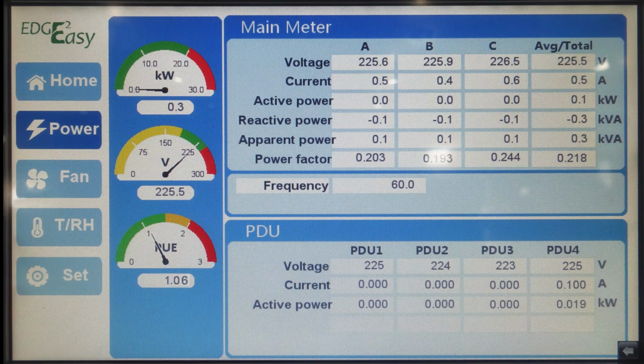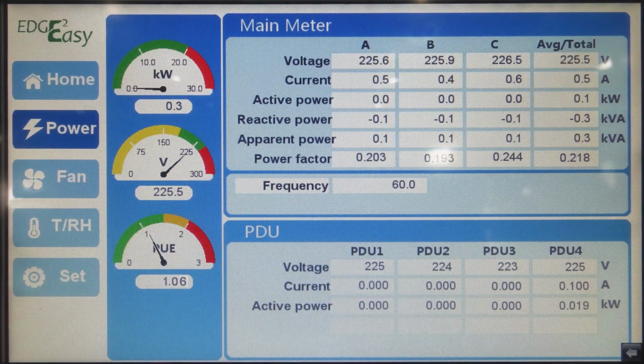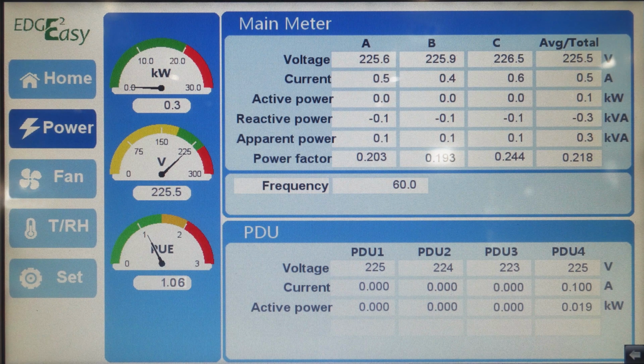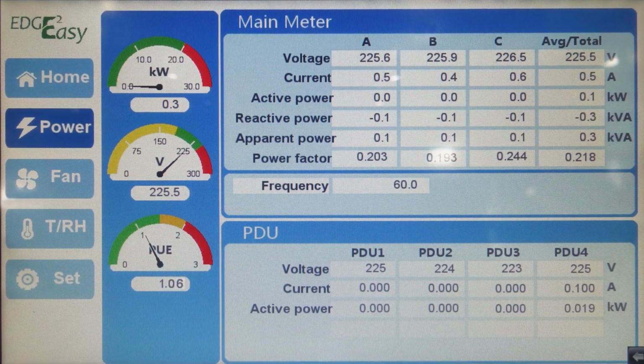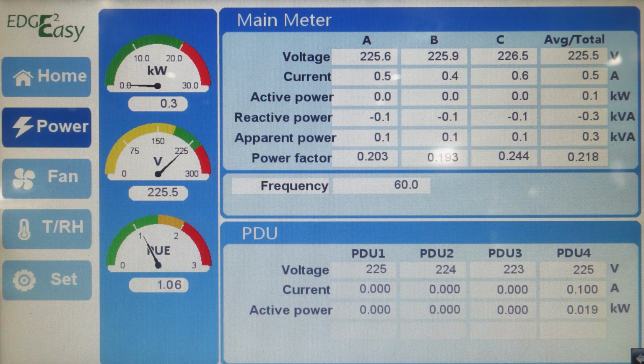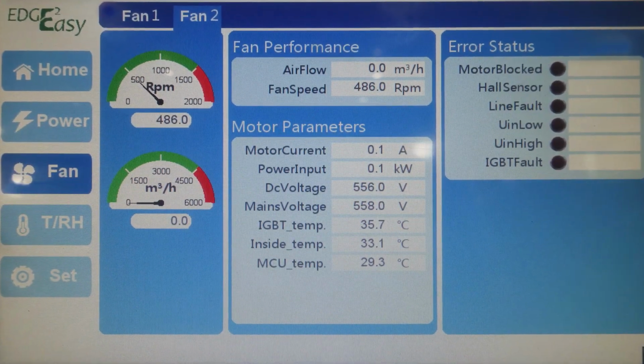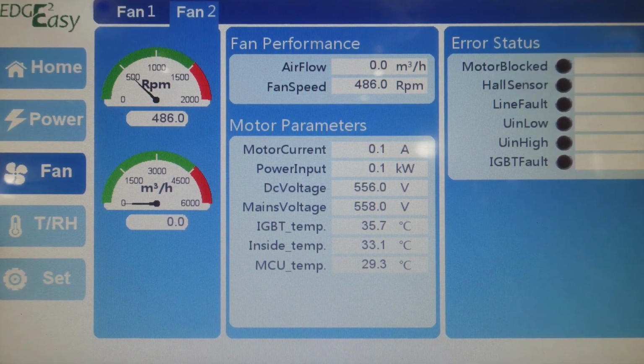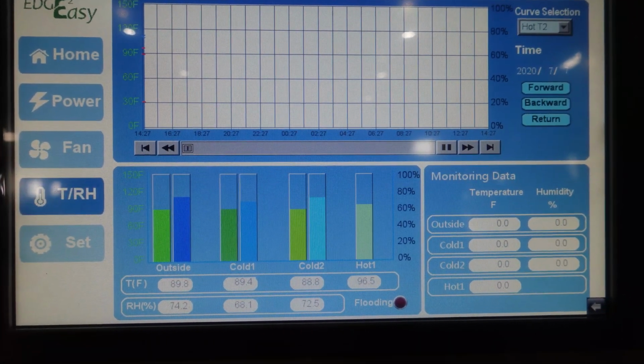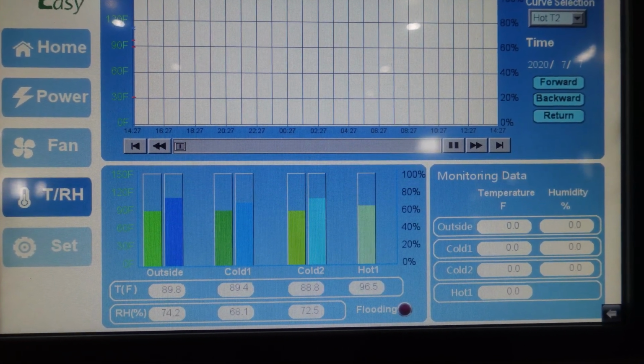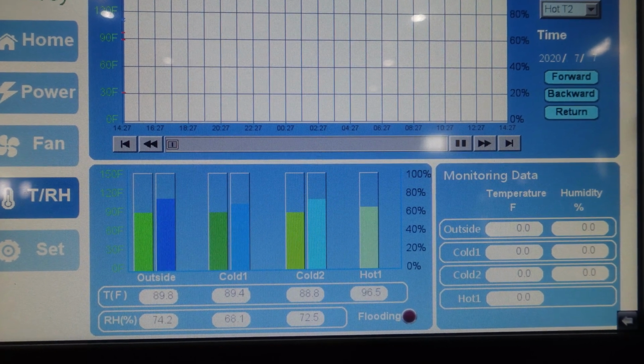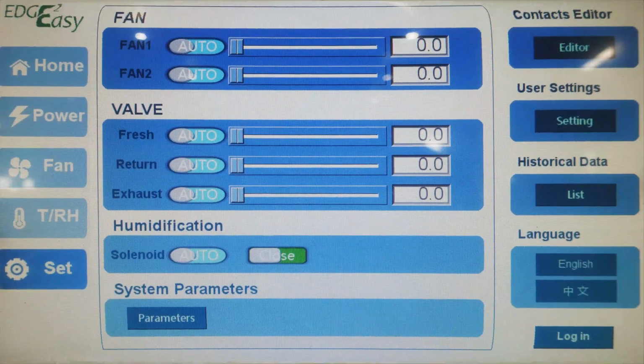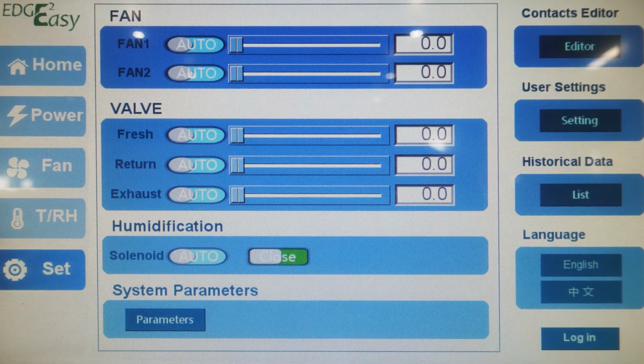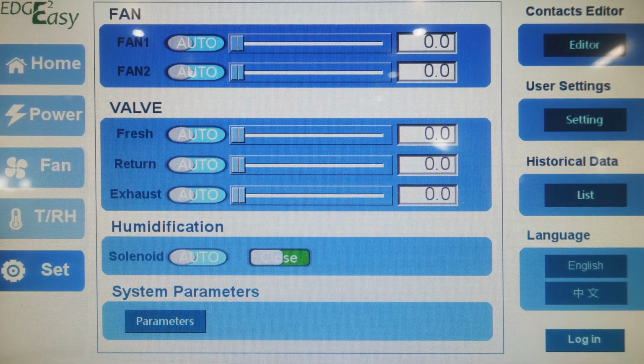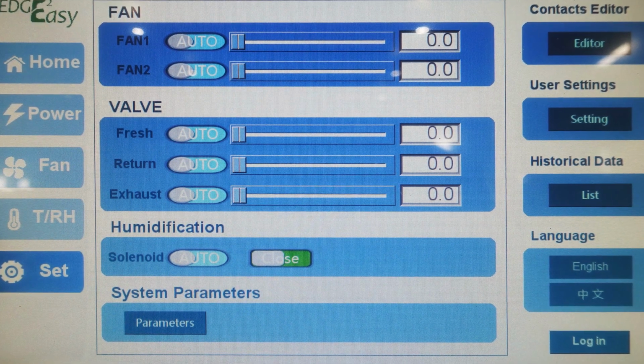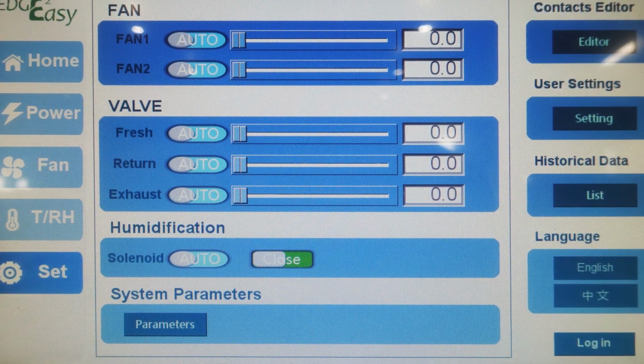From the power screen, you can see the real-time energy consumption and monitor the performance of the intelligent PDUs that manage the power for everything that is plugged into the racks. You can make sure the fans are performing properly and also troubleshoot any issues. You can track the temperature and relative humidity in real time, and there is a graph that shows historical data. From the settings screen, you can manually adjust the fans, humidity, and dampers, monitor the filters, and update other add-on features such as security cameras, alarms, and more.